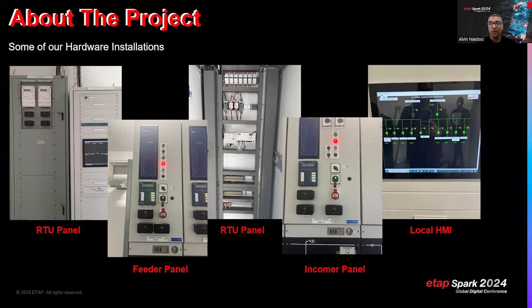So going forward, on the SCADA architecture, we chose a simple architecture where at the substation level, all of the RTUs had an embedded layer of cybersecurity on them. Speaking to the master station, we chose a common protocol of IEC 104. They then communicated and fed into the network layer that had another layer of cybersecurity on them, which inevitably fed to the primary server and hot standby. We chose the server configuration as a redundancy aspect.